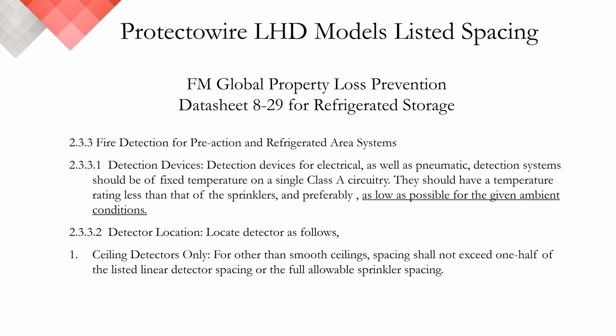For refrigerated storage, FM Global Property Loss Prevention Datasheet 8-29 states that the lowest temperature detector should be selected and that for other than smooth ceilings, the detector spacing should not exceed 1/2 the listed spacing, or the full allowable spacing of the sprinkler. Protectowire's PHSC 135 XLT and the newly introduced CTI 135 XLT both have the lowest activation temperature of any digital linear heat detector on the market and developed specifically for the refrigerated applications.